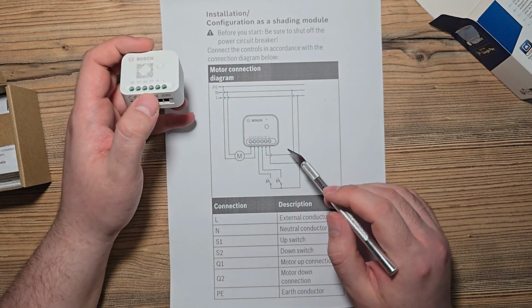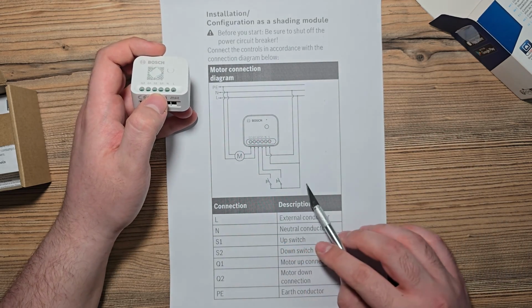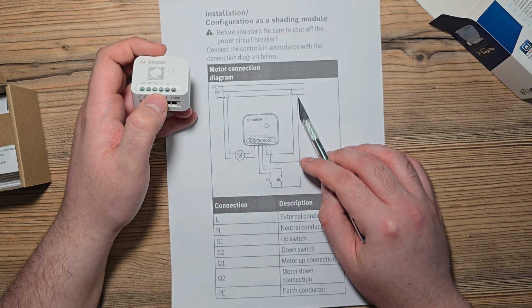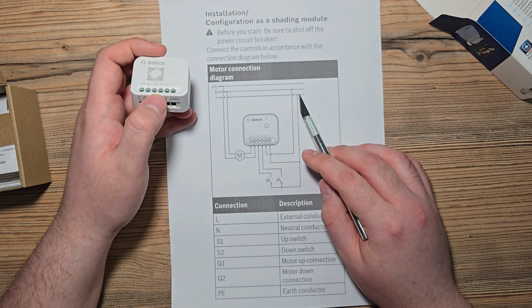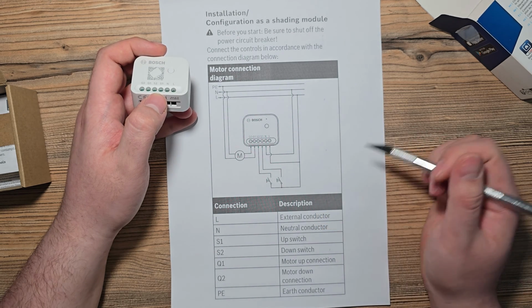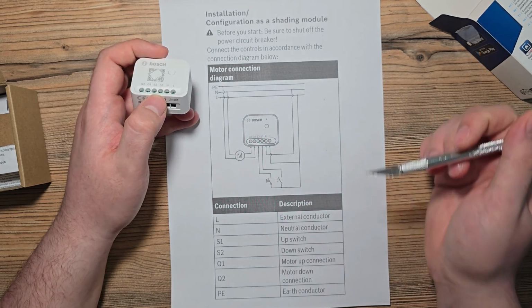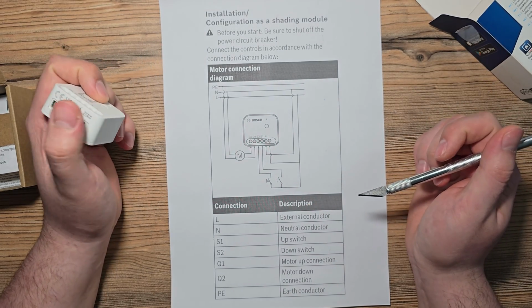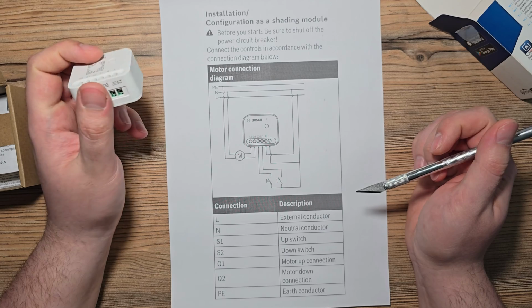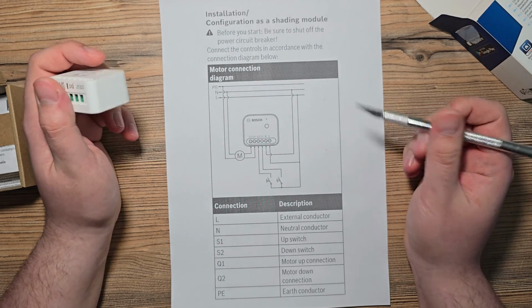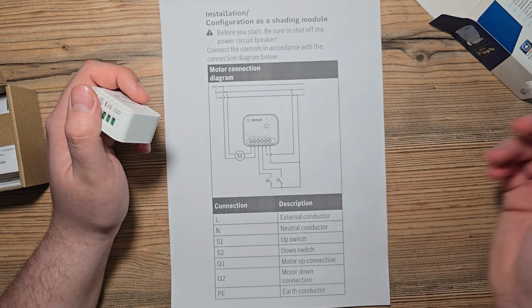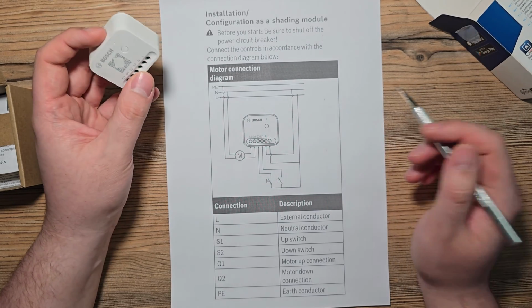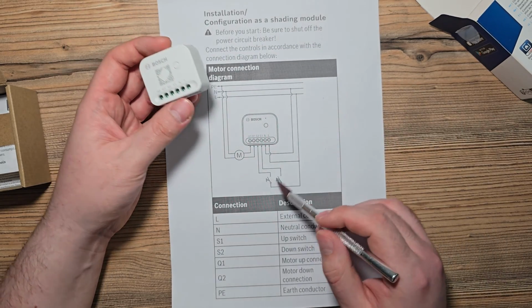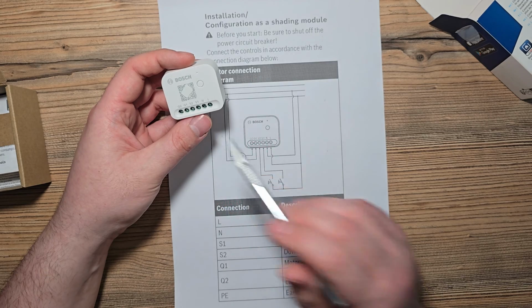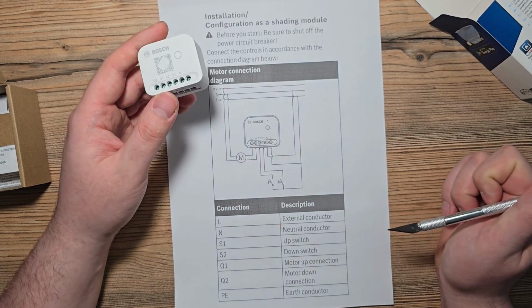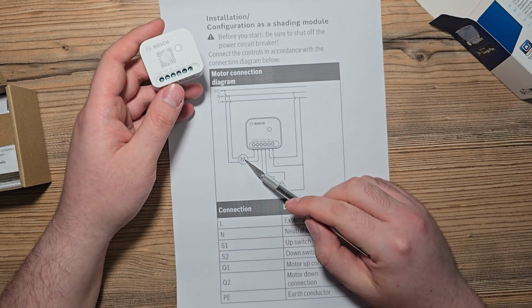And as we can see on the schematics, those are connected to live. So we are getting high voltage on the switch pins. Be aware of that, because I saw some other drivers which have only a low voltage signal with the direction of blinds, and be aware that we've got high voltage on the S1 and S2. And next we've got the motor connection.